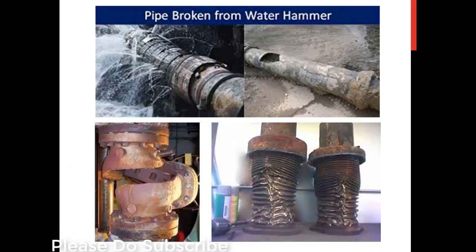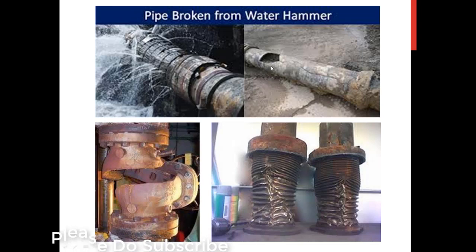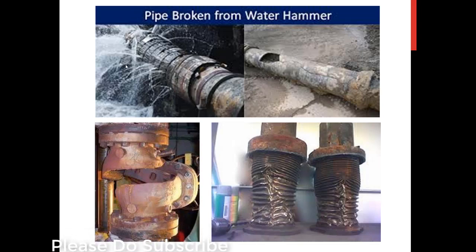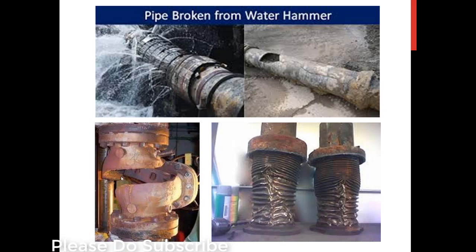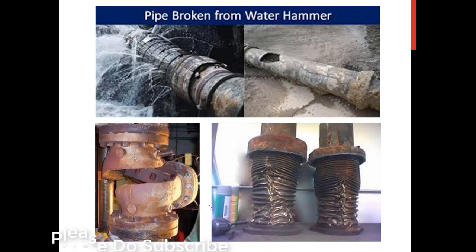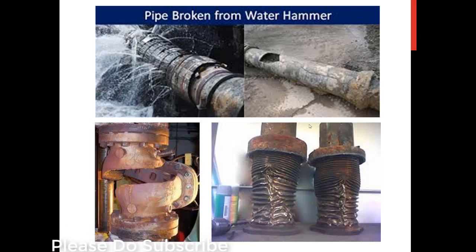I'll show you the images of sudden pressure rise and the breakage of those pipes and the damage at different junctions. These are the bellows where due to sudden pressure spike the damage has been occurred. It is very clearly visible the damage that the sudden pressure spike can cause.